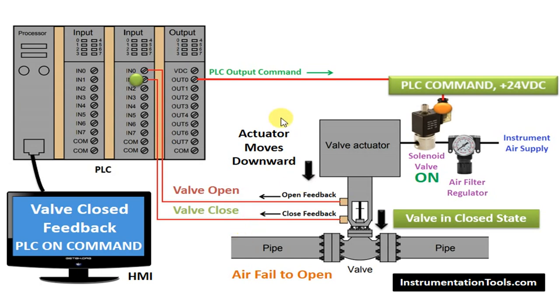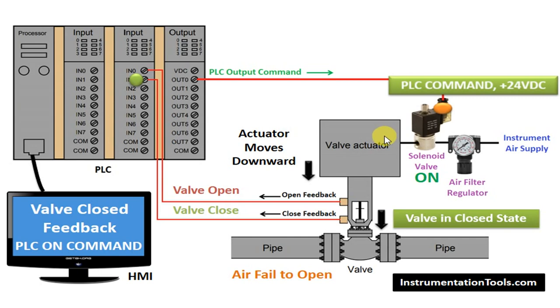For example, now the PLC will remove the command from the PLC. So, the power which is coming to the SOV will be removed. That means the SOV will be de-activated — it will go to off state. Once it goes to off state, there will be no air supply to the valve actuator. Already, some air will be there inside the actuator. That will also be vented outside via another port. So, the spring in the valve makes the actuator return again, to make the valve state change from closed state to open state.